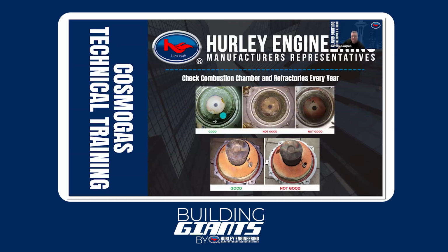Here are just some examples of what you can see. You can see the photo on the left. Even though this is not brand new, it's definitely in good shape. You can see this kind of discoloration. This is normal operation. This is what happens when you're operating in a condensing environment and you have that moisture all the time. But it doesn't look bad. Now, when I get to these, you start to see the darker colors. You can see how the water seems like it might have pooled up onto the bottoms of the refractory, and it's just generally darker all around.